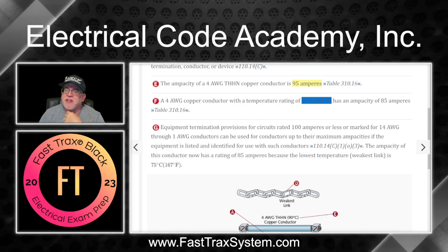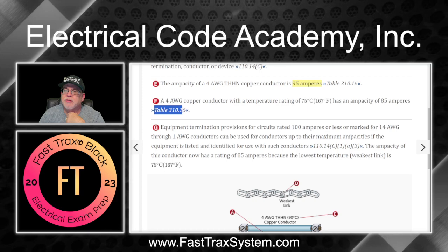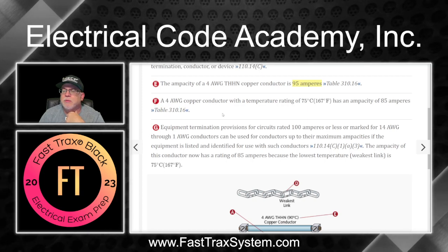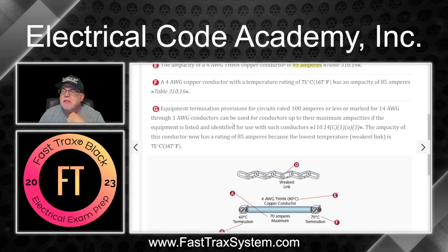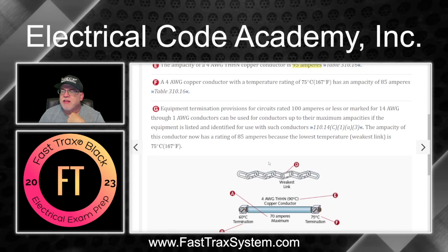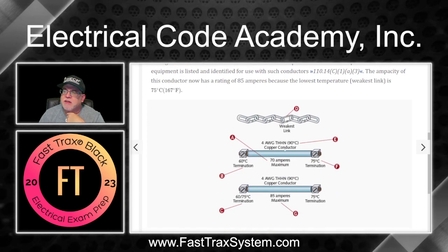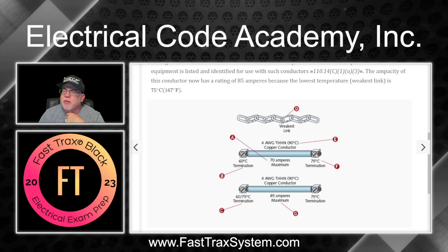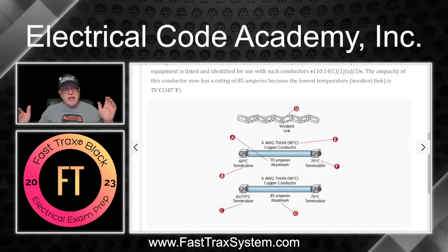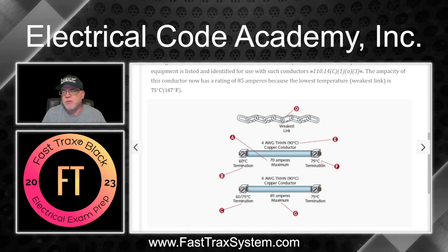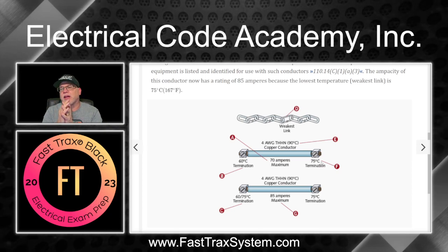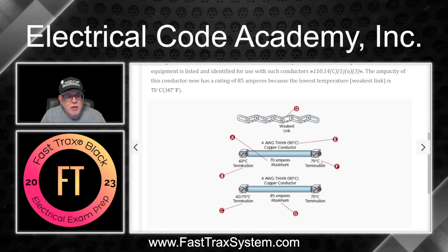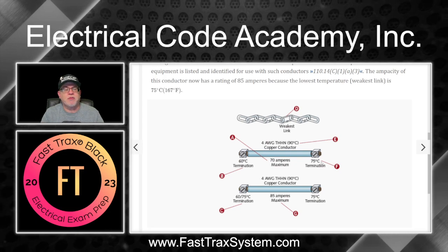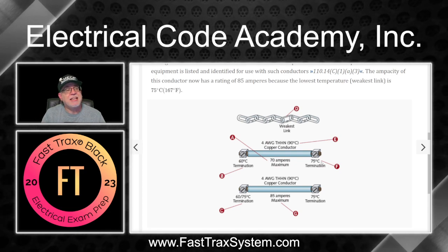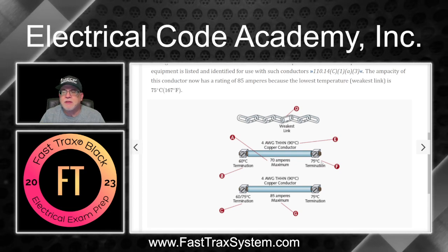So we've already established that. We went and looked at 310.16 to establish that. So we get that. One of the takeaways from this is if you were to take this conductor here and remove the terminations of the conductor, and you had a question, and then somebody said, what's the ampacity of a 4-gauge THHN? Well, that's easy. It's 95 amps. Well, then they say, well, can I use all of that 95 amps?